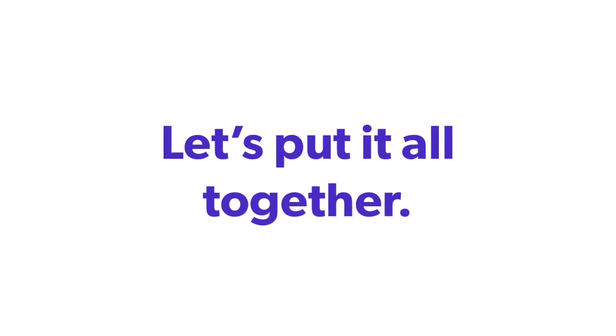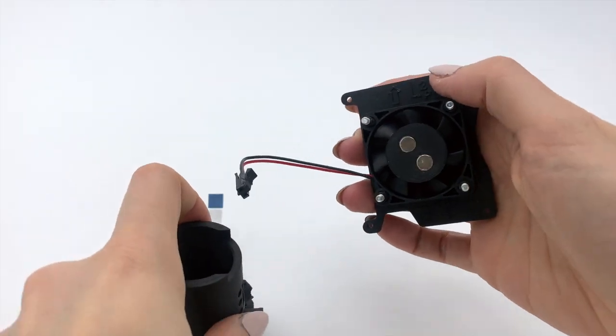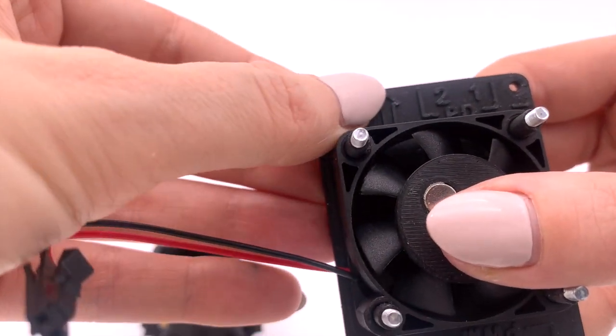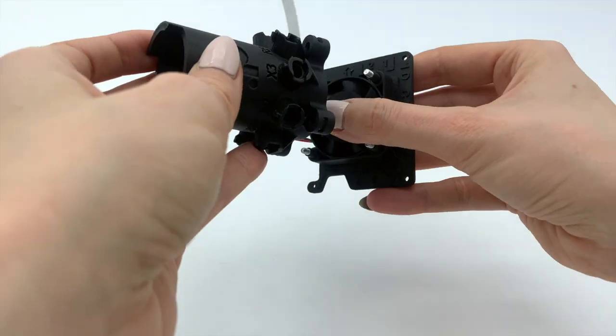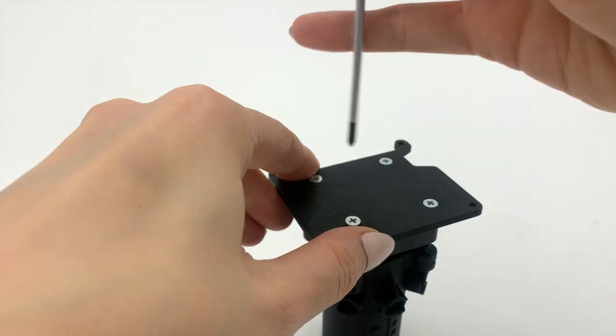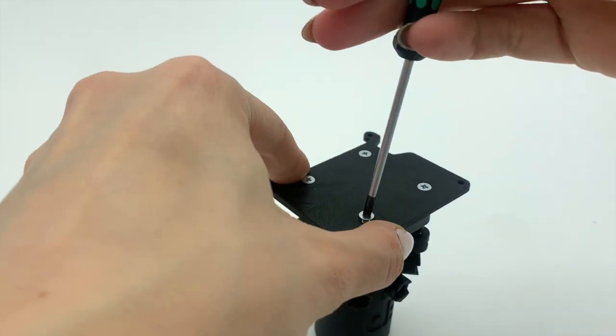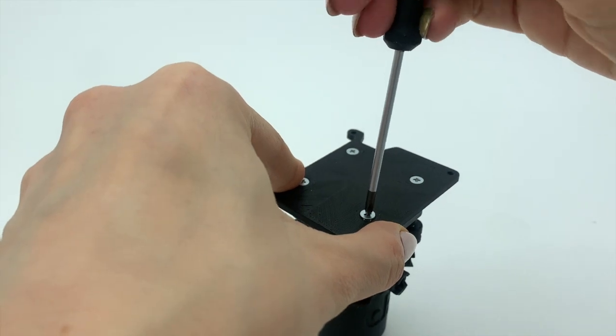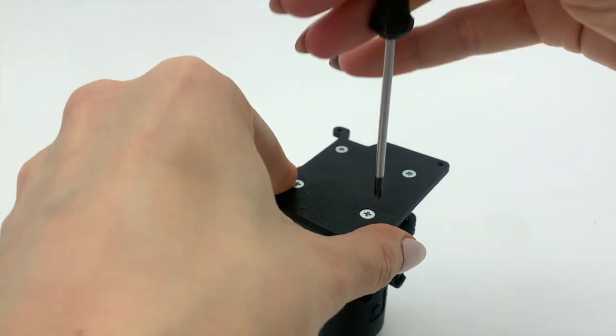Okay, let's start putting it all together. Orient the vial holder so that the flex cable is on top of the arrow. Secure the vial holder onto the faceplate by tightening the screws. Do not over-tighten. The head of the screws should be flush with the faceplate.